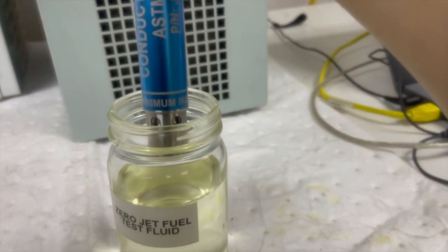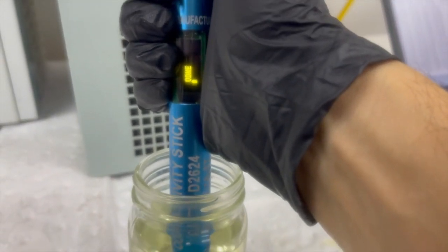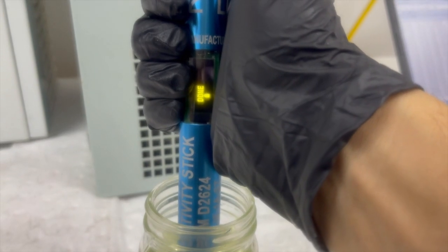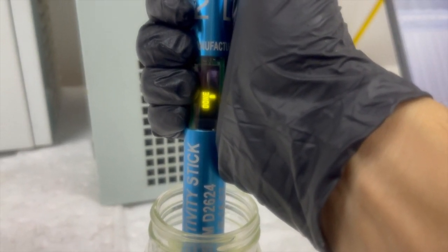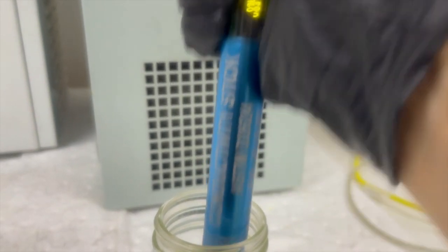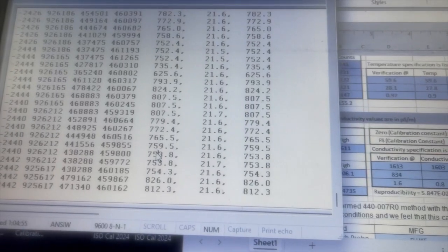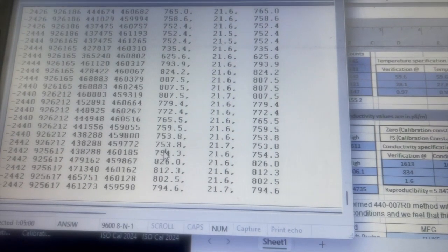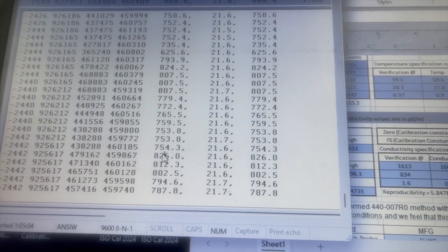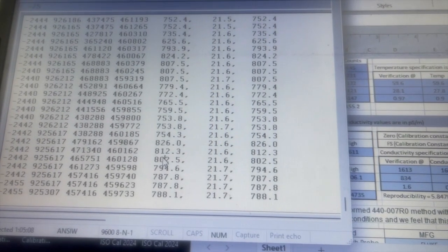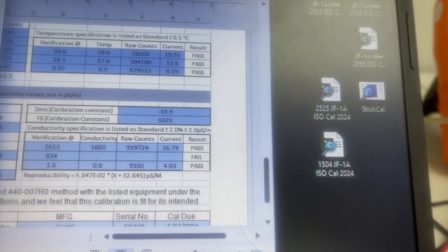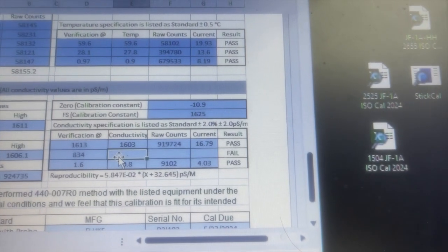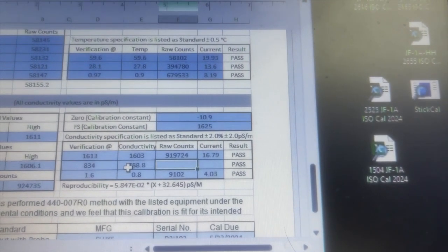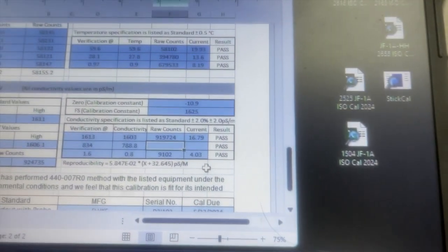Okay, now we're going to get our middle value. So we have our middle value fuel here. We use our reference instrument, the handheld stick, to get our value. Value of 834 picosiemens per meter. We'll plug that into our little chart, 834. And now let's get our numbers from the inline itself. When we check it against it, we're getting counts of 826, 812, 794, so about 788. So we go over here and plug that in: 788.8.